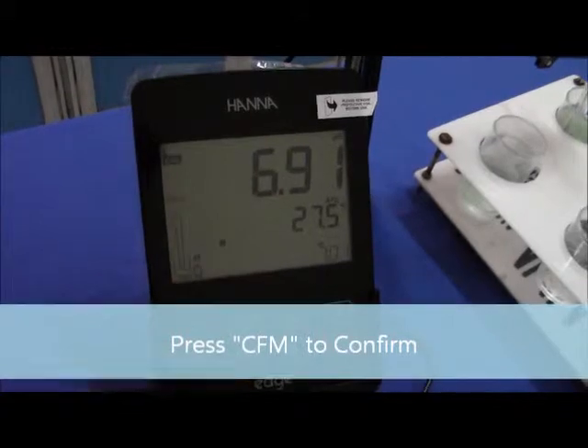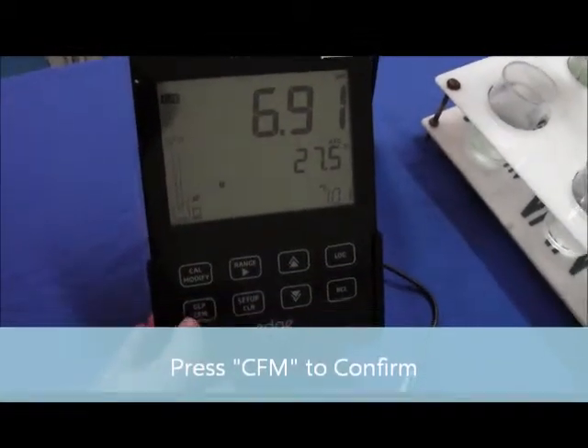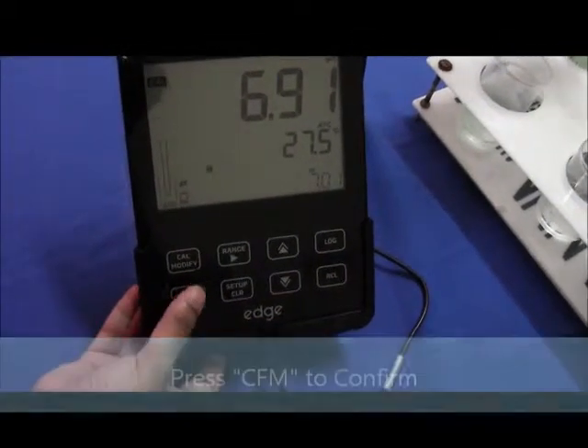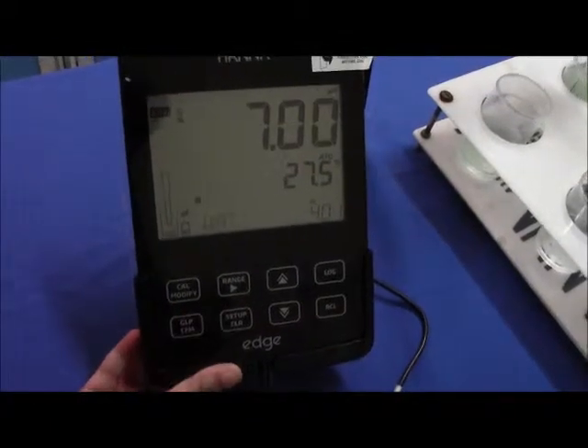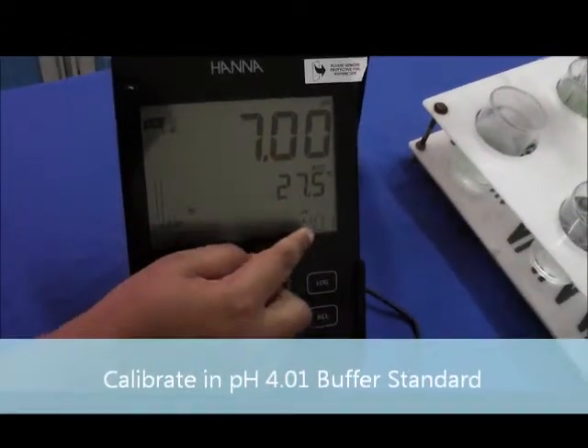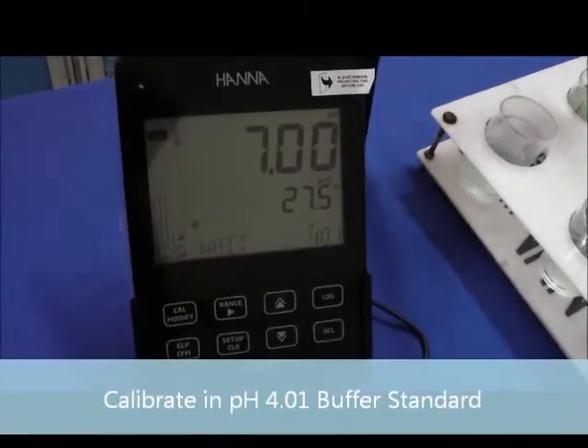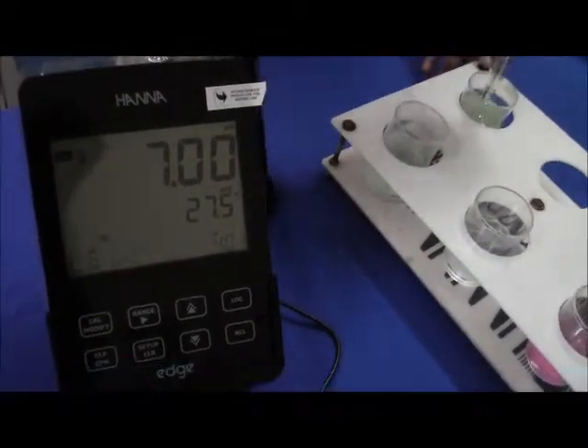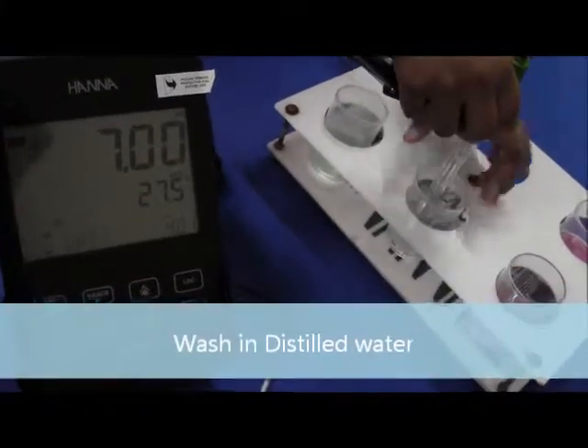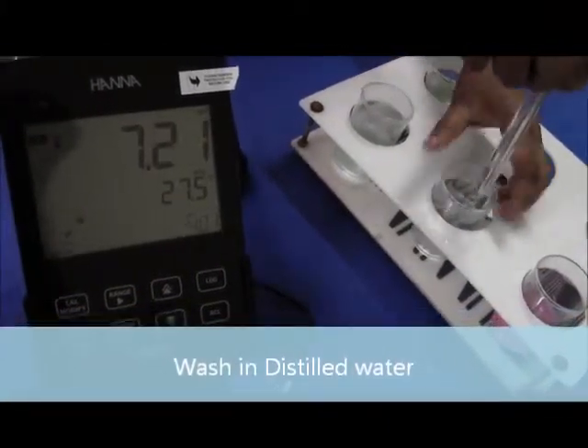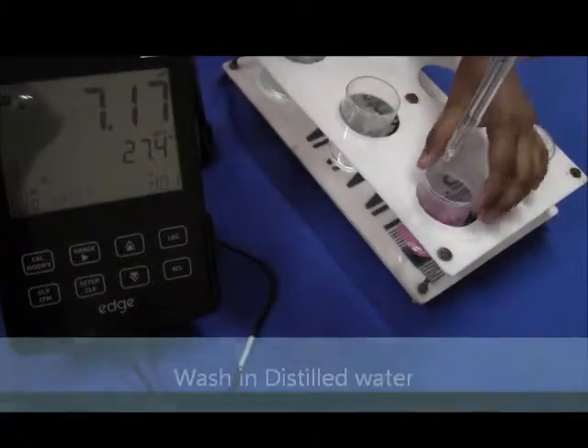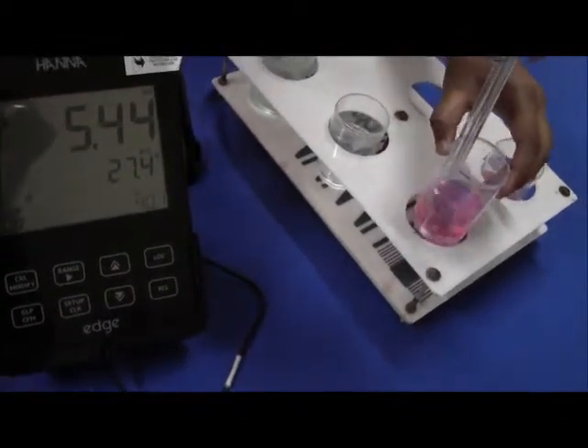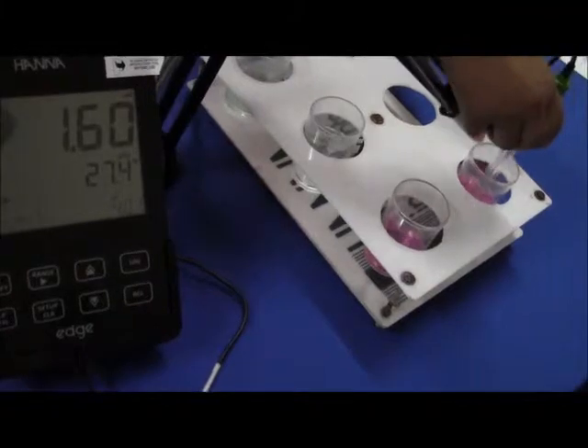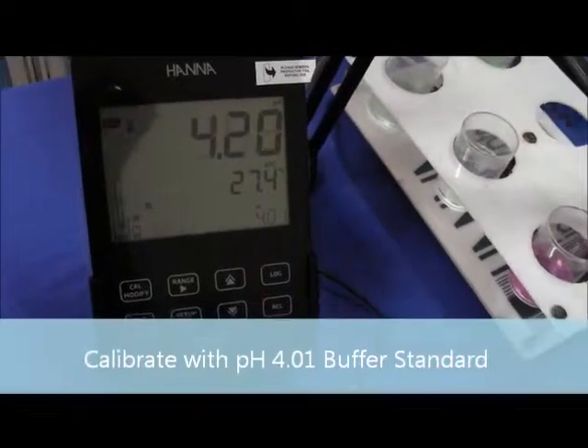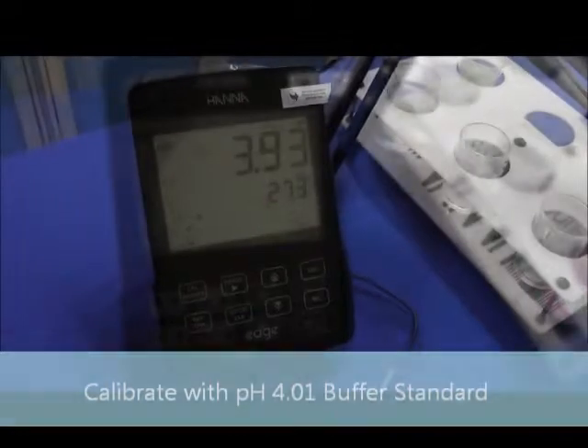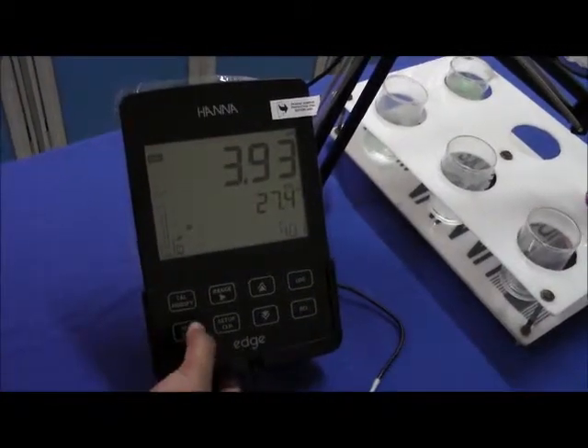Once the CFM signal is blinking on the meter, press the confirm button, which is just below the calibration button. Now the meter is asking to use pH 4.01. Rinse the electrode in distilled water and now immerse it in pH 4 buffer. You can again confirm the reading.